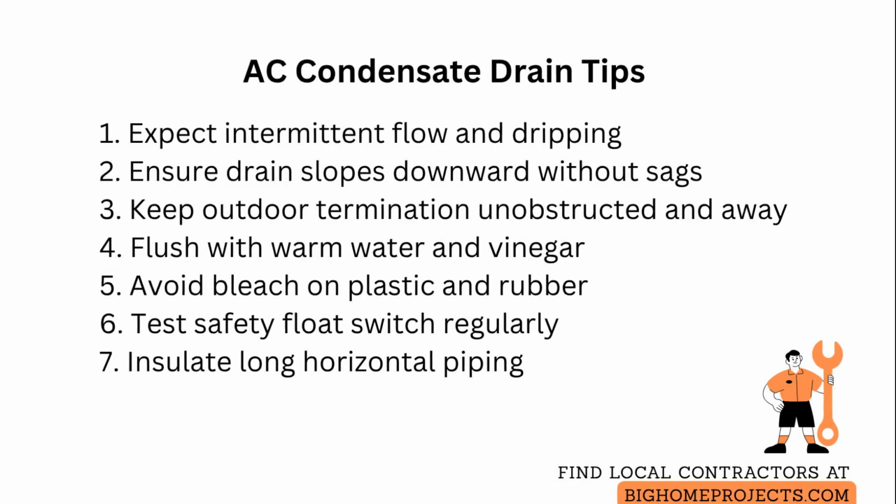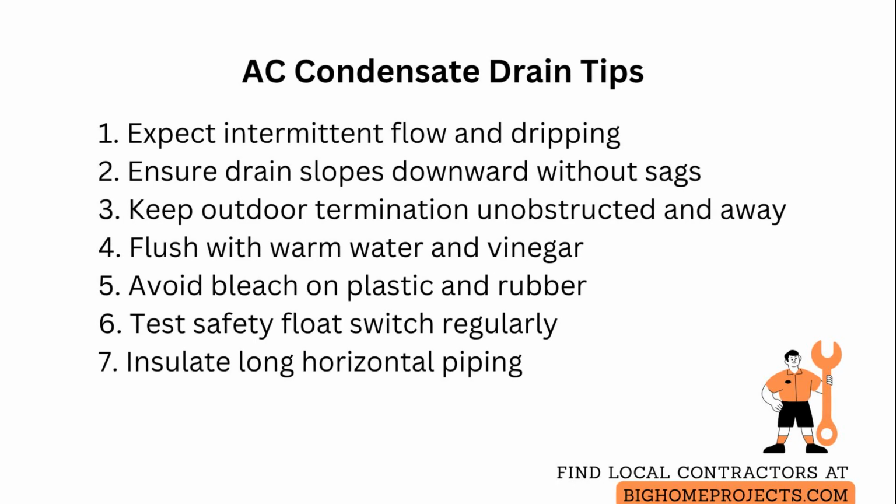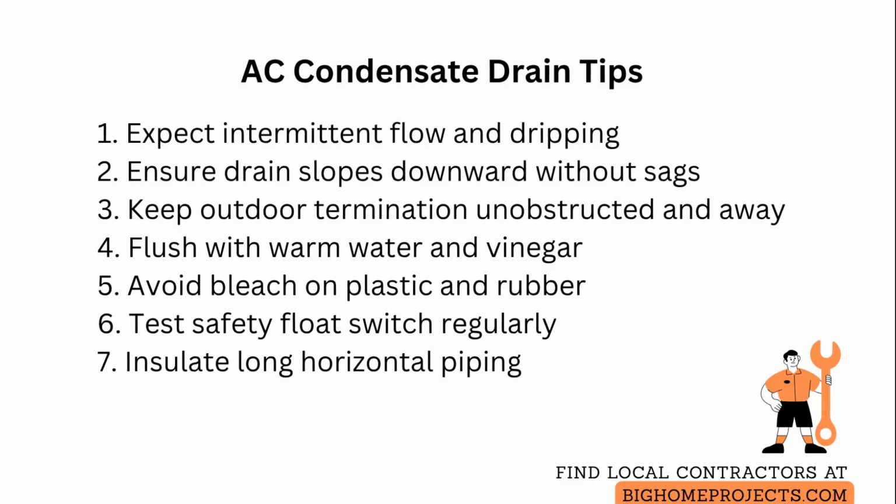If you have a secondary safety float switch or condensate overflow switch, test it by lifting the float gently to confirm the air conditioner shuts off and then resumes when the float is lowered.